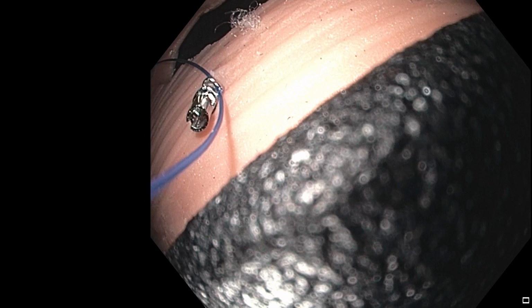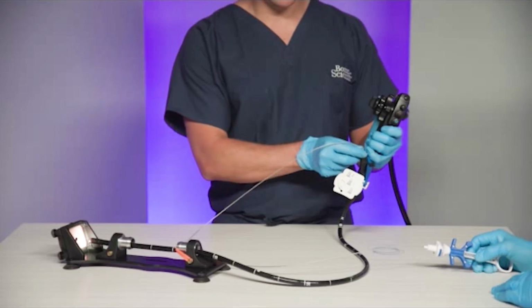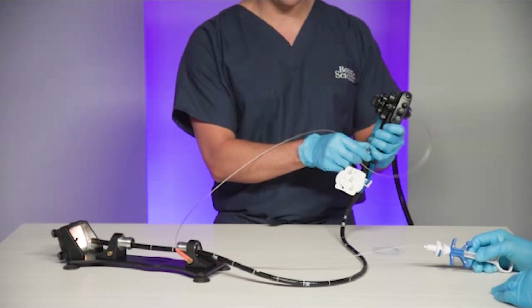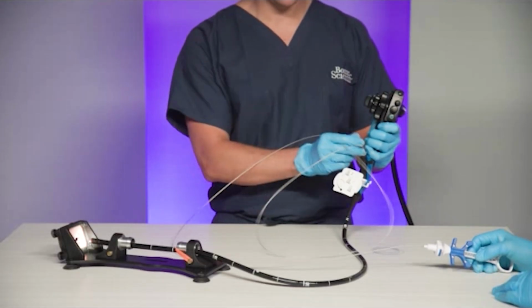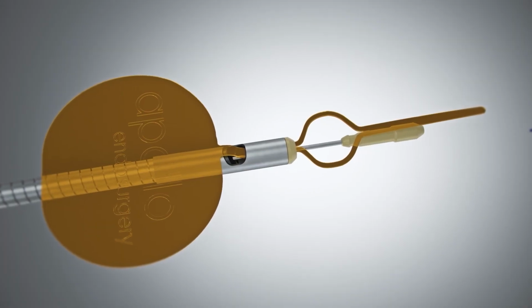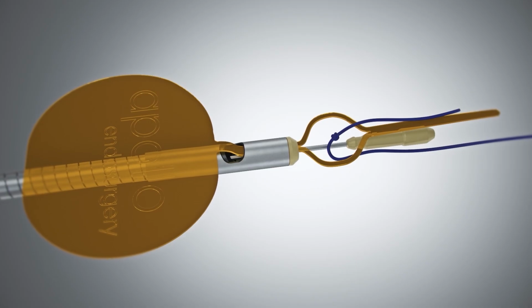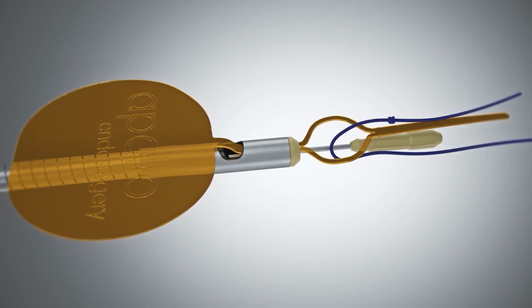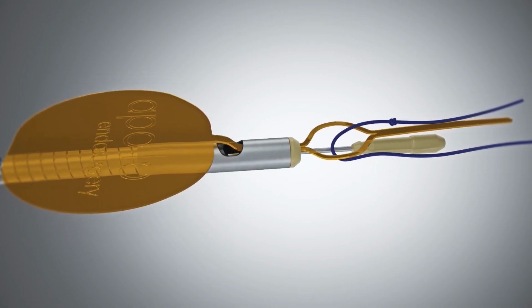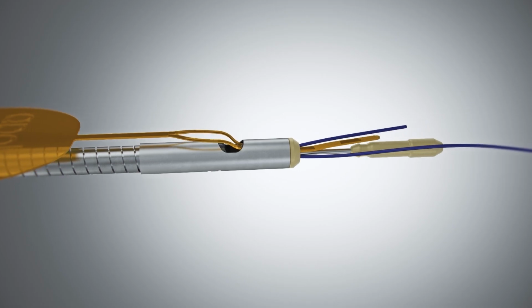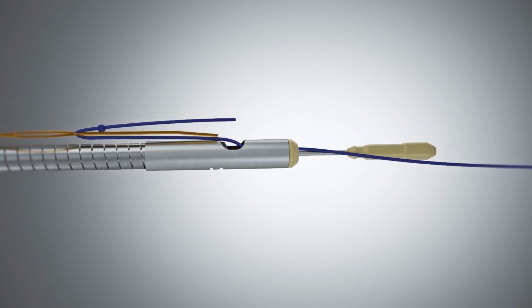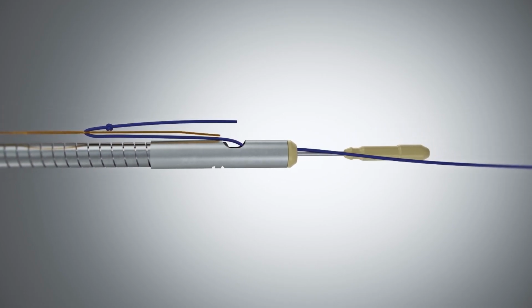After the fourth and final helix tack placement, remove the device catheter and scope liner from the working channel, leaving the suture in place. To load the cinch, thread approximately 3 centimeters of the proximal end of the suture through the gold suture loading loop. Pull the gold tab in line with the catheter until the suture has passed through the PEEK collar.